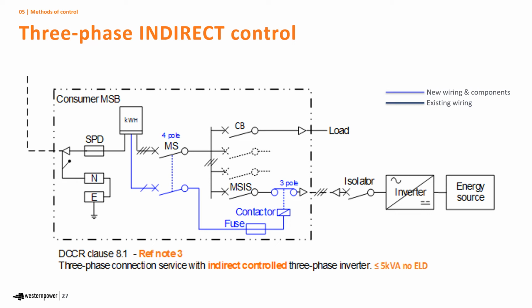In almost all situations, a three-phase connection point will need to be using indirect control. It's similar to the single-phase indirect control, but the differences are you'll need a 4-pole main switch circuit breaker to provide that additional pole on the main switch for the auxiliary terminal. You'll always be using a contactor, but it'll be a 3-phase contactor to switch the 3-phase inverter, and you'll need fuses to protect the control cable to the contactor.